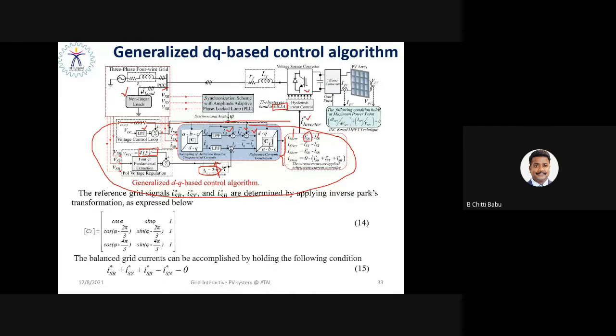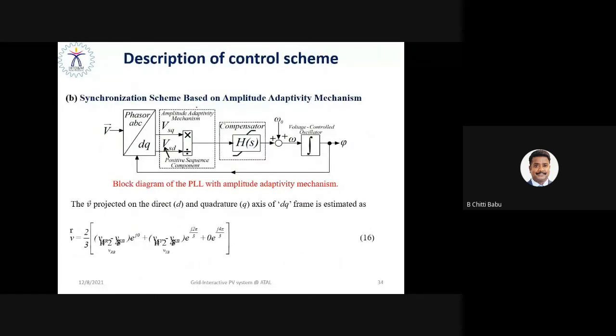Here we use grid synchronization in order to decouple ABC to DQ. We need the component called phi, which is the phase angle detection. For phase angle detection, we use a grid synchronization tool, the phase locked loop. It consists of a phase detector and comparator, a loop filter, and a voltage controlled oscillator. So we are able to estimate the fundamental phase angle.